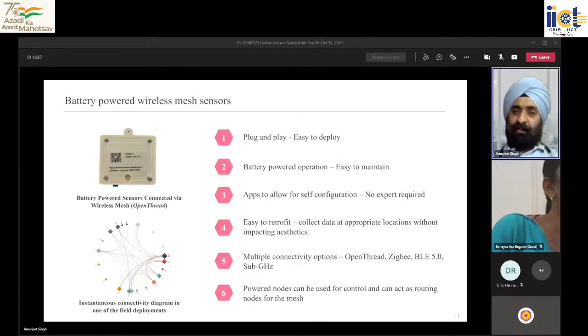Think of this control node as what people in the automation world commonly call a DDC, digital controller, or direct digital controller, or a PLC, programmable logic controller. Think of this as a wireless PLC or wireless DDC, which has analog digital inputs and outputs, to which you can connect any sensor or actuator talking over standard protocols like 0 to 10 volt, 4 to 20 milliamp, 24 volt digital, 230 volt digital, Modbus, etc.